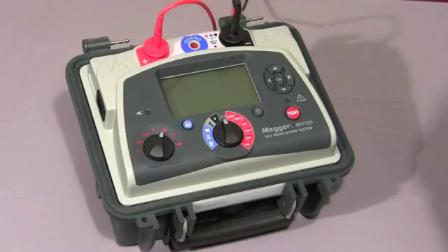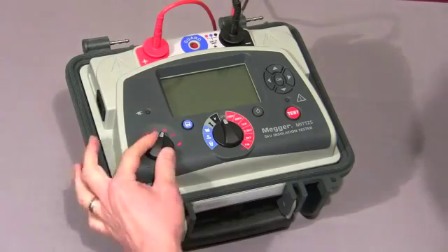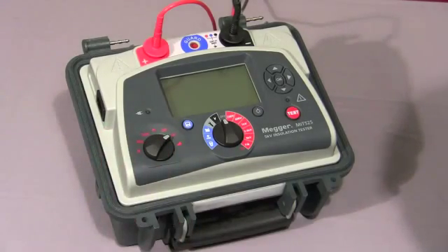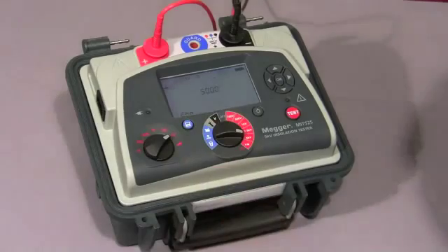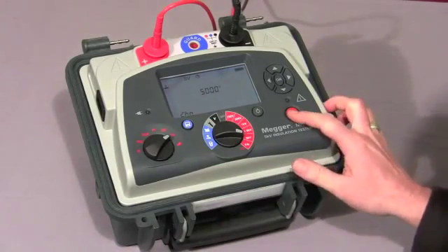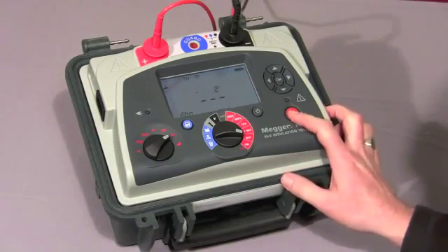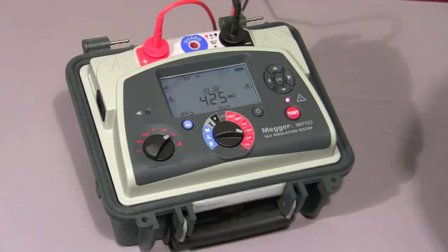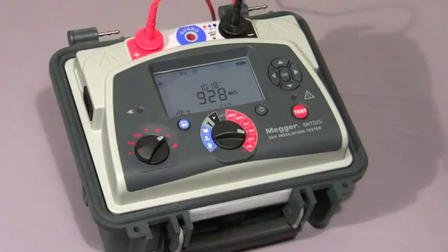Next, I'll show you a step voltage test. We select SV on the mode switch. We select our required test voltage, then press and hold down the test button until the test commences. The instrument will increase the test voltage in 5 equal steps. In this case, because I've selected 5 kV, the instrument will increment in 1 kV steps. The default time for this test is 5 minutes, so each step is 1 minute long.